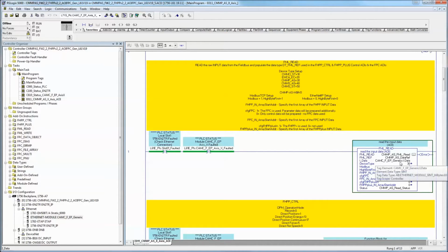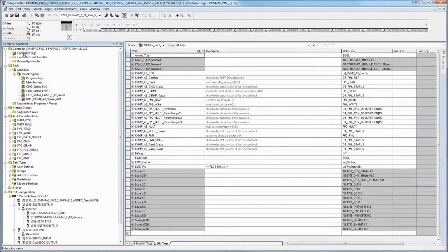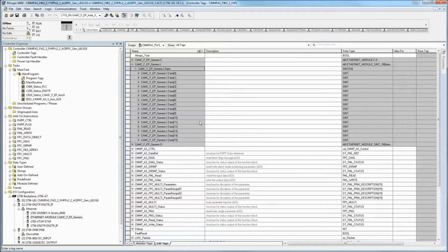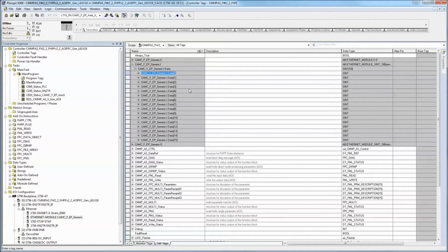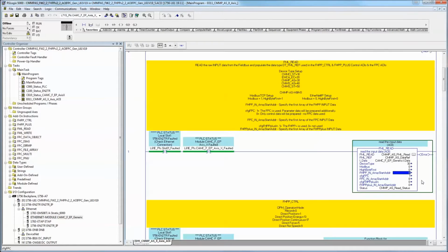Okay. So we've added a generic module. So this generic module here is shown right here. So we have our 16 bytes. So this tag right here is what we reference to this iData here. And we could have a variety of things in the same, there's quite a few configuration options, but this here, we're specifying our first byte. So in our circumstance here, byte 0 is our starting address. This can be different, but in this case it's not.